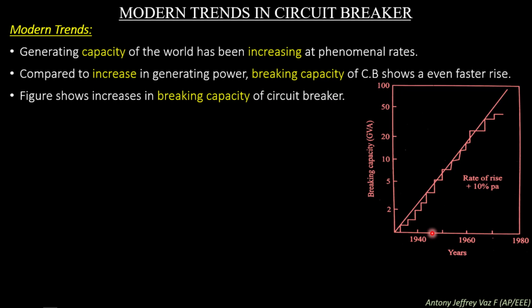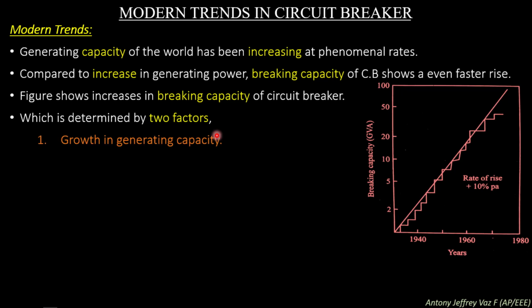Here in the x-axis you can see the years, and in the y-axis you can see the breaking capacity of a circuit breaker in GVA. So as the years increase, the breaking capacity is also increasing at a faster rate, which is determined by two factors. The increase in breaking capacity of a circuit breaker is determined by two factors. One is growth in generating capacity. Second, an increasing trend towards interconnection of systems.